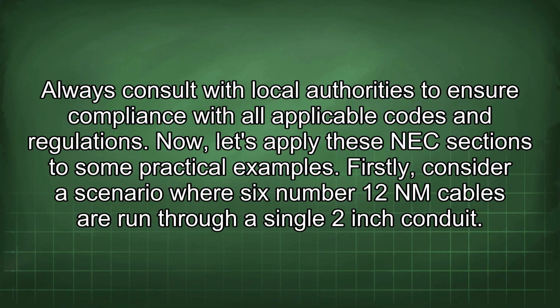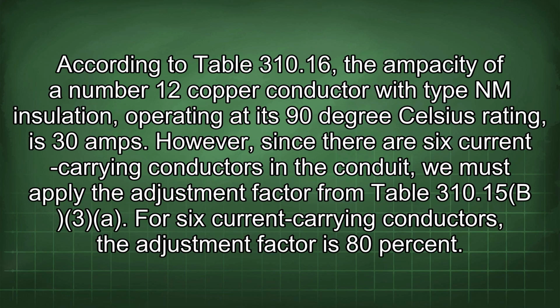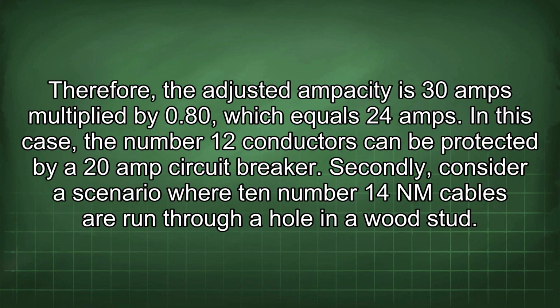Firstly, consider a scenario where 6 number 12 NM cables are run through a single 2-inch conduit. According to Table 310.16, the ampacity of a number 12 copper conductor with type NM insulation operating at its 90°C rating is 30 amps. However, since there are 6 current carrying conductors in the conduit, we must apply the adjustment factor from Table 310.15(b)(3). For 6 current carrying conductors, the adjustment factor is 80%. Therefore, the adjusted ampacity is 30 amps multiplied by 0.80, which equals 24 amps. In this case, the number 12 conductors can be protected by a 20 amp circuit breaker.